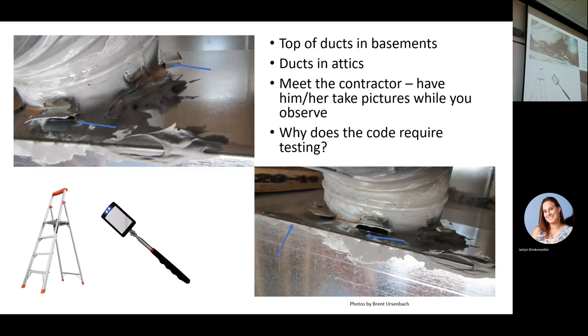I think that was ridiculous because you just... Anything that's snap lock. Now I can see if your lock former machine for your snap lock is not adjusted right, it's a pretty sloppy joint. And yeah, I can see that would leak a little bit, but 6-inch pipe or whatever, when you snap it together, it's not leaking. And so actually that got stuck in the code, and then a bunch of us pushed to get it out, because if it's inside the envelope, why would we, it's just the leakage is minuscule compared to all the other places.